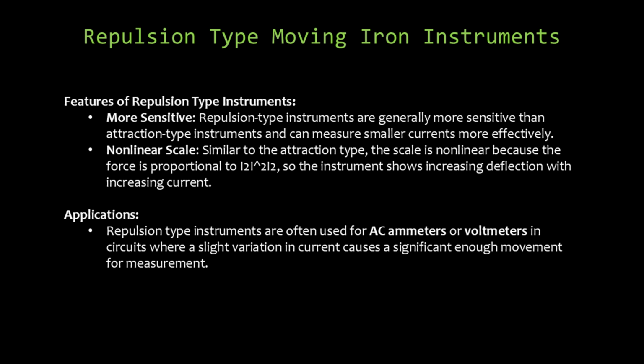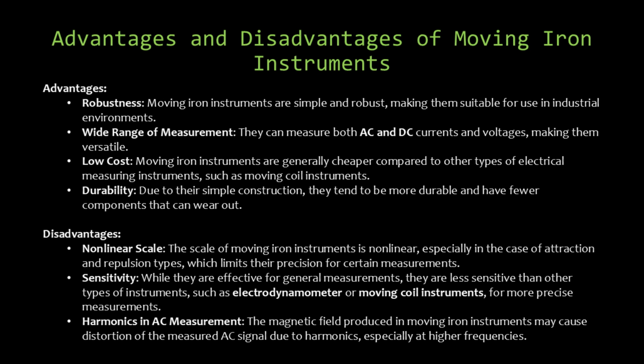However, like attraction-type instruments, they also exhibit a nonlinear scale. This means that the deflection of the instrument is not directly proportional to the current, which can affect the accuracy of measurements, especially for precise readings. Repulsion-type instruments are often used in AC ammeters or voltmeters, where a slight variation in current can cause a significant enough movement for measurement. Moving iron instruments offer several advantages, including their robustness, versatility, low cost, and durability.